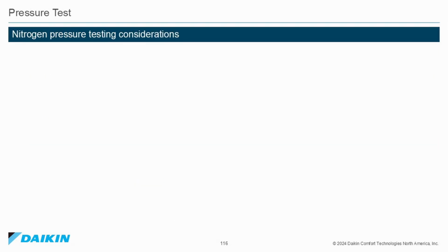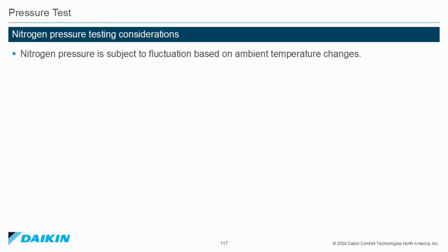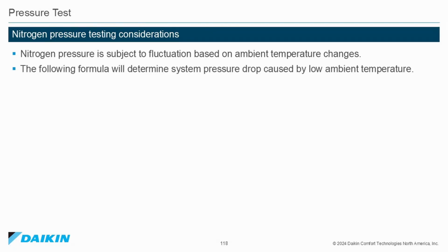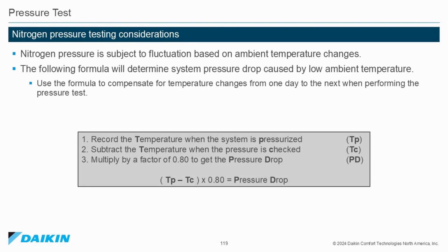Pressure test. Nitrogen pressure testing considerations. Nitrogen pressure is subject to fluctuation based on ambient temperature changes. The following formula will determine system pressure drop caused by low ambient temperatures. Use the formula to compensate for temperature changes from one day to the next when performing the pressure test.